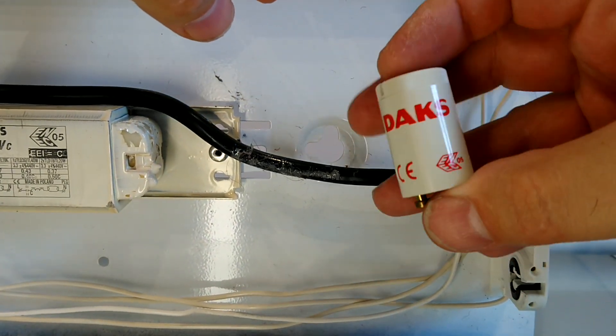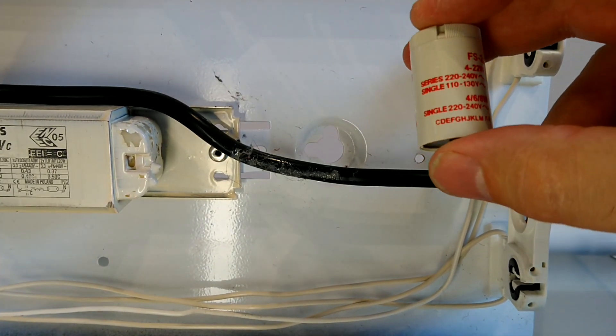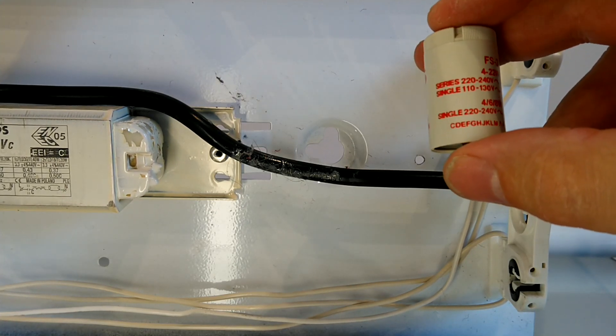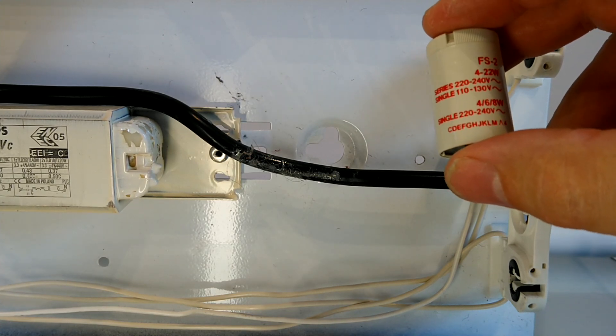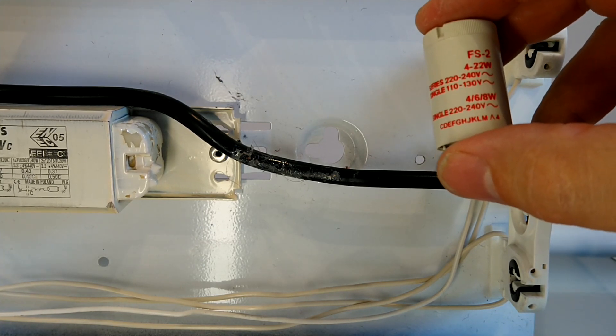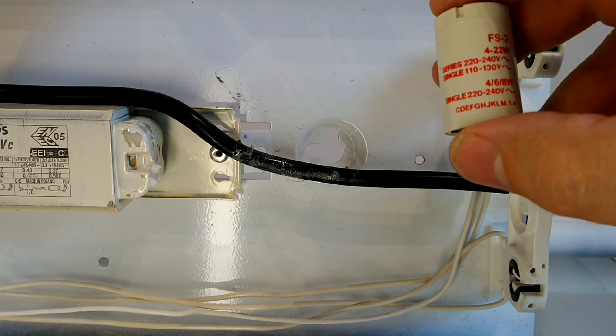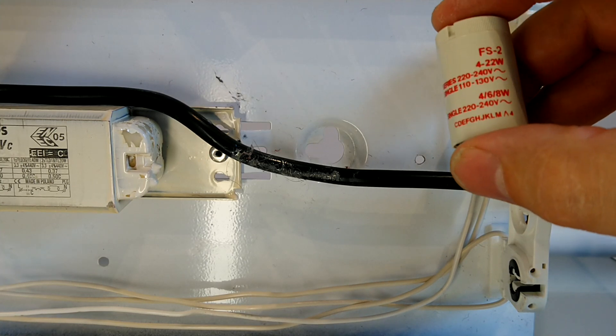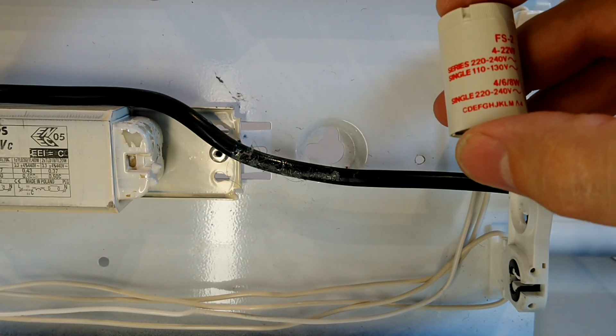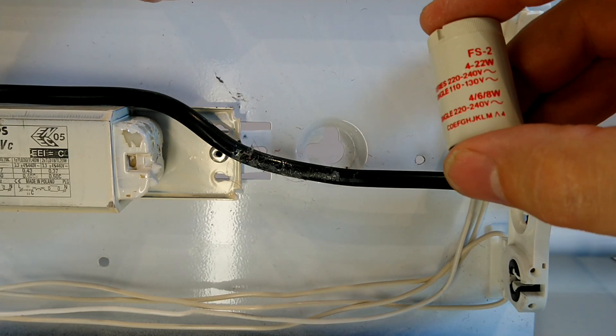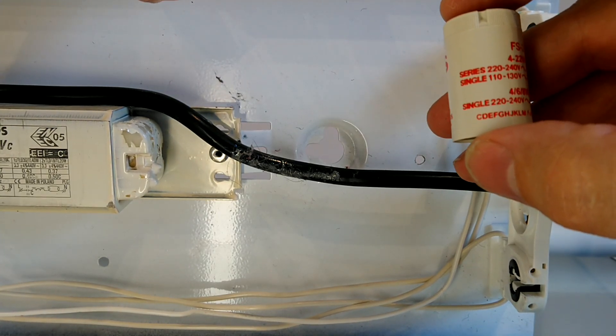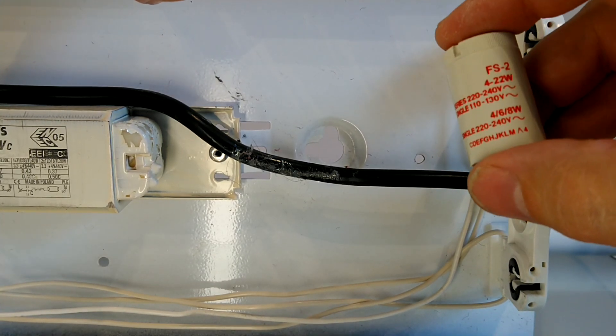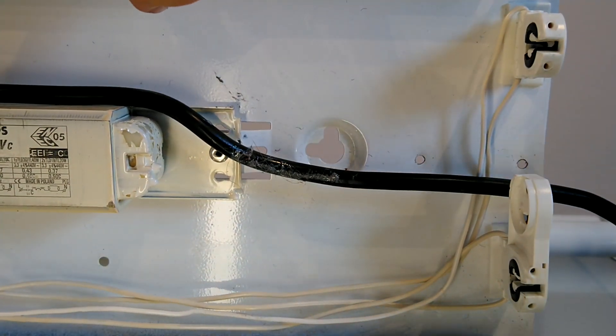I have no idea where these starters are from. DAKS, some information. And these are FS2 4 to 22 series single and series pairs. They can use these in America apparently on the lower voltage to light up 4 to 22 watt tubes at 110 to 130 volt. And then they can also be used as singles in the UK and Europe at 220 to 240 volts, 4 watt, 6 watt and 8 watt fluorescent tubes. And then they can be used as series pair starters between 4 and 22 watts, which is what they've been used for in this light fitting.